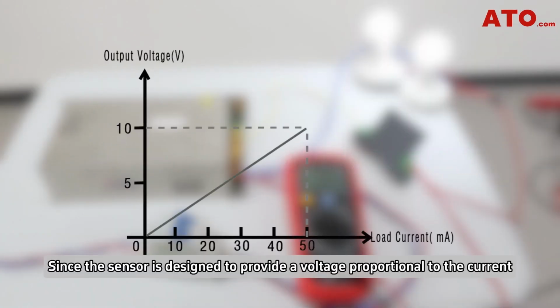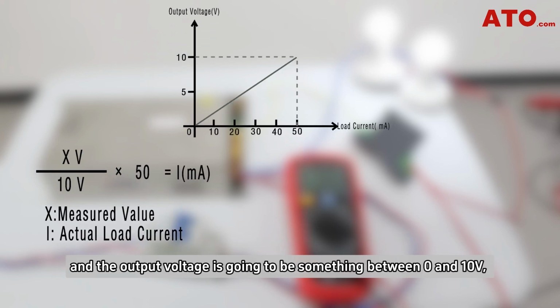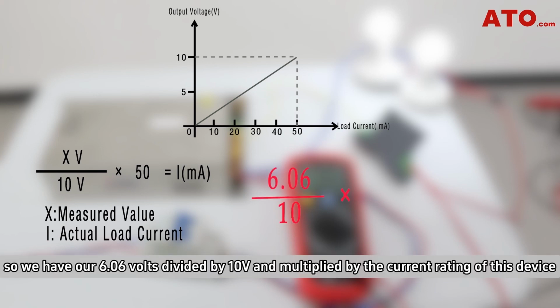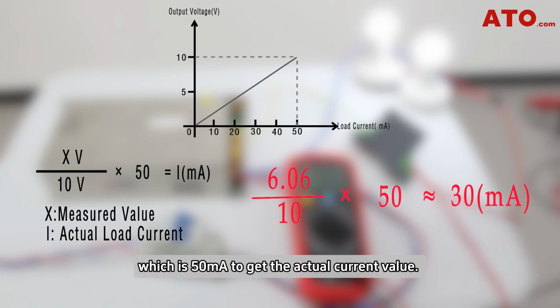So how does that work out? Since the sensor is designed to provide a voltage proportional to the current, and the output voltage is going to be something between 0 and 10 volts, we take our 6.06 volts divided by 10 volts and multiply by the current rating of this device, which is 50 milliamps, to get the actual current value. That gave us about 30 milliamps.